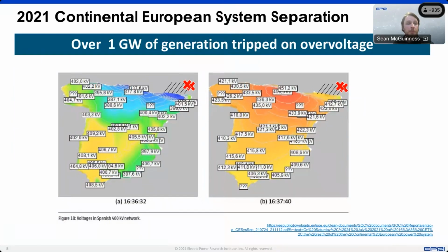So a number of shunt reactors started switching out, and then as the other lines between France and Spain began to trip, and the frequency declined and under-frequency load shedding kicked in, the loss of load combined with the loss of those lines actually drove the voltage up. Now, the shunt reactors had already switched out because of the undervoltage condition. So now we swung from an undervoltage condition to a large overvoltage condition. So you can see on the 400 kV grid, it went up to a peak of about 450 kV, well above their 1.1 per unit limit, or 1.05 per unit normal operating range. So you can see this large swing in voltage was a characteristic of this last event in 2021.